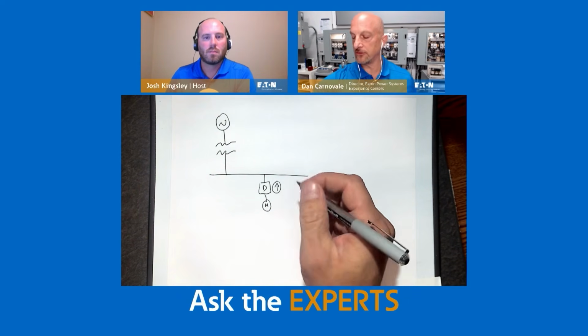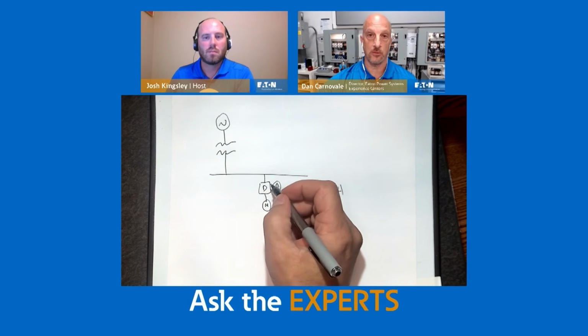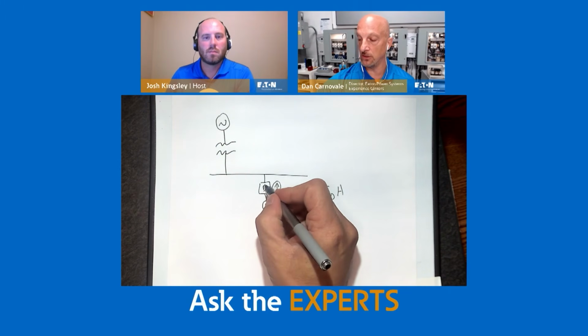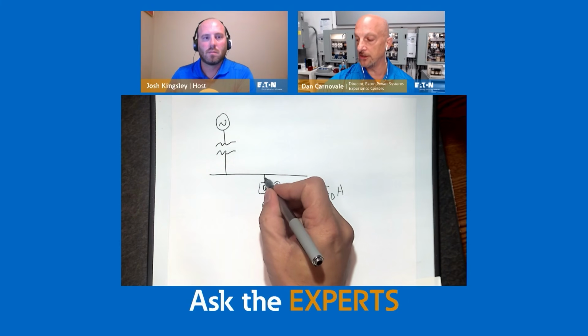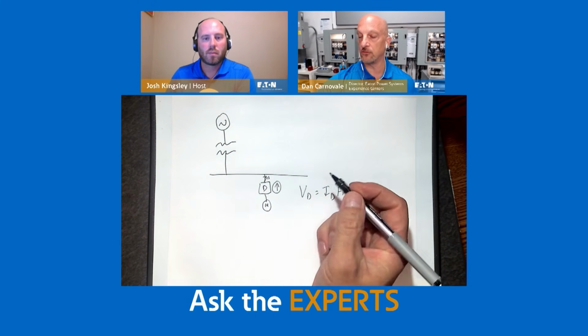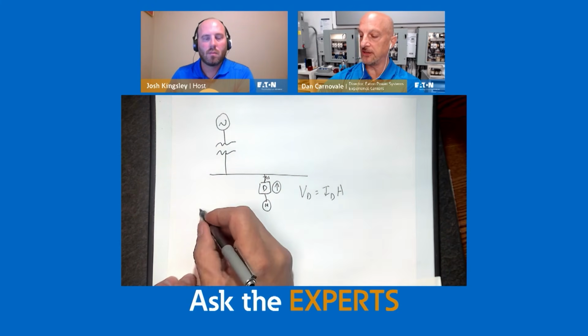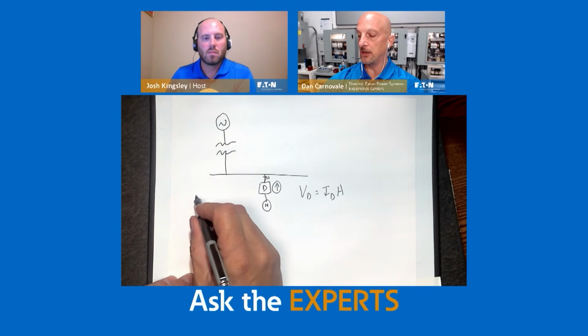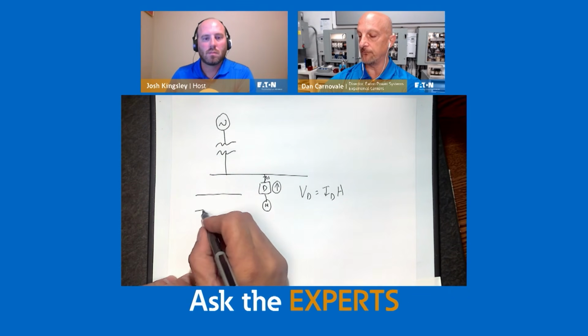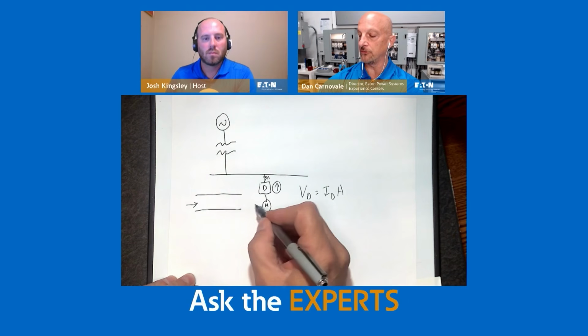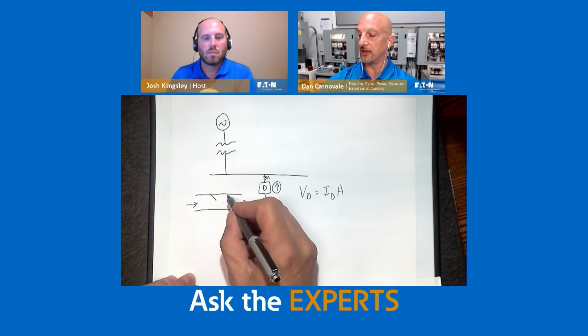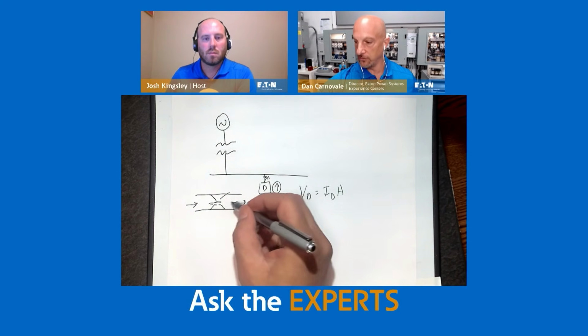So what are some of the solutions? Some of the solutions I would start with: DC chokes built into the drive, or line reactor built into the drive, or an additional line reactor in front of the drive. And what that does is basically constrict the current. So I always think about it like water coming through a hose. If I constrict that hose, we've all pinched a hose together, you get a higher pressure out the other end, but we're really limiting the flow through there.